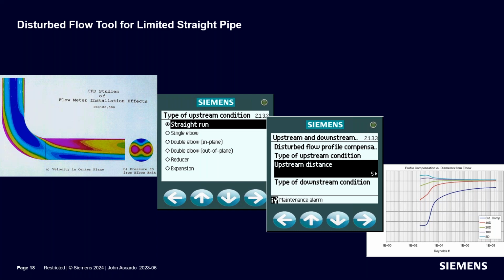Something that Controlotron pioneered and developed and deployed back in the '90s program, and it's been in every flow meter since, and it continues to be in the FS230. And it's just simply a matter of picking your flow condition. What is your pipe geometry? In the menu, single elbow, you have double elbows in plane, double elbows out of plane, reducers, expanders, and how far away they are. And by doing so, you see on the right flow profile correction curves that are variable, that are a function of data that you've entered to correct for the actual flow profile condition. So that gives us the ability to work with limited straight run and still maintain a high degree of accuracy.